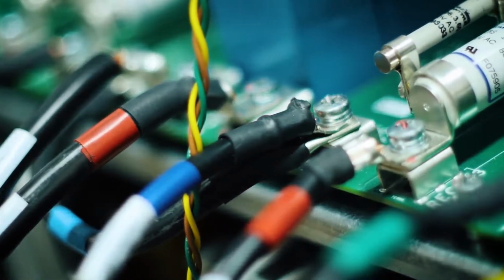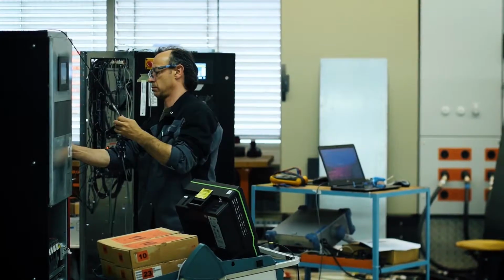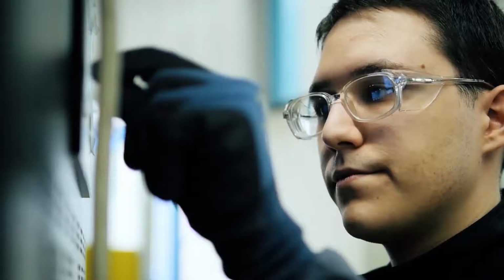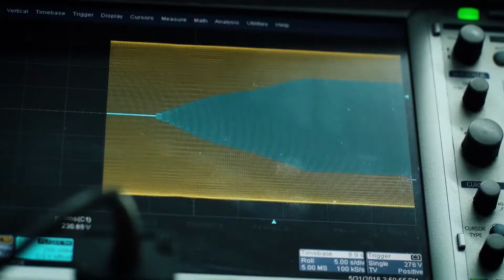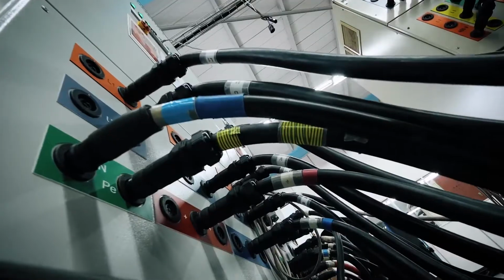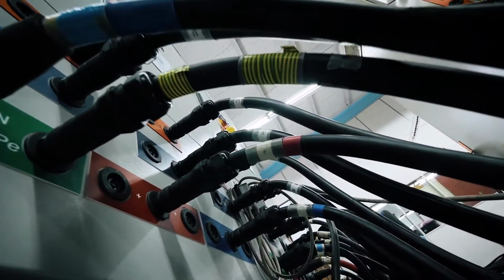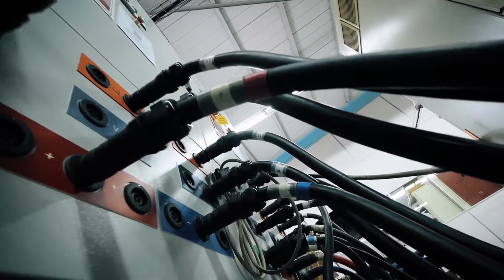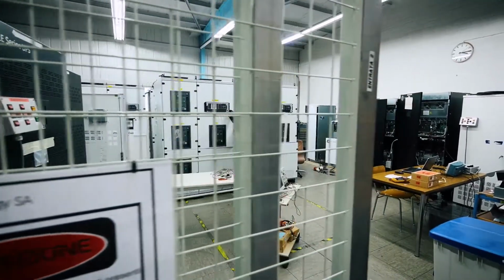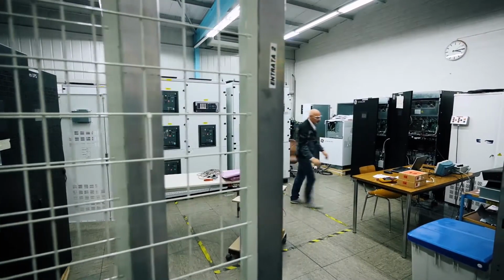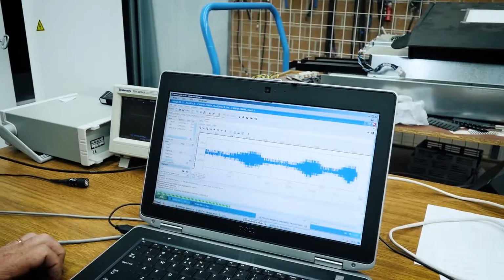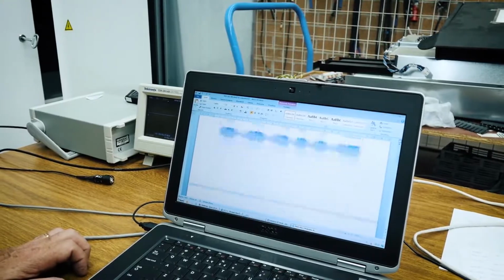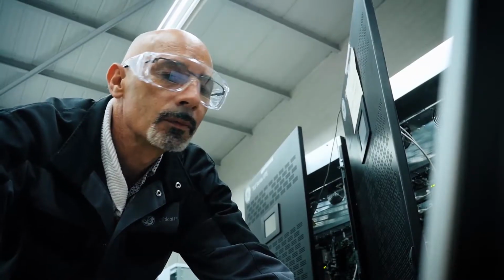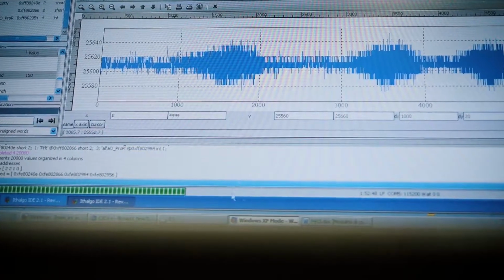A standard protocol includes measuring efficiency, input and output harmonic distortion, overload, step load tests and a short circuit test. In the overload test, UPS should stand a load 1.5 higher than normal for a minute. Moreover, on request, GE can also perform extra tests and provide a tailor-made protocol to satisfy customer expectations completely. A non-linear load burning test, component failure simulation and a connectivity demo are good examples of activities typically required.